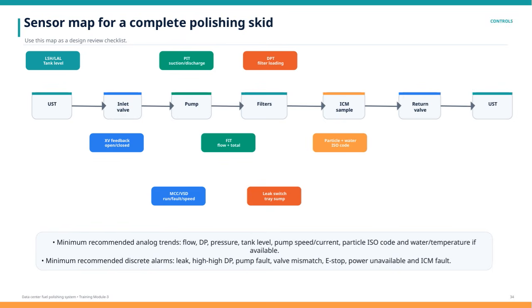Likewise, essential discrete alarms should include leak detection, high differential pressure triggers, pump faults, valve mismatches, emergency stops, power unavailability, and ICM faults. Using this sensor map as a design checklist helps ensure comprehensive monitoring and control of the fuel polishing system, ultimately safeguarding operational efficiency and fuel integrity.